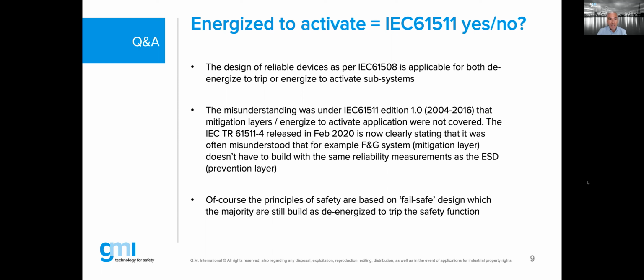Now, if you use that sensor in your area where the gas is available in a certain quantity, the purpose of the sensor is, of course, to sniff and recognize the gas. If the gas is blown by the wind in the wrong direction and there is no coverage by your gas sensors, that will not make the sensor reliable, because the sensor cannot even measure it. So the coverage, the mapping of your sensors, is just as important as the SIL2 on that specific device. But what is SIL2 on that device saying? That, provided the sensor is able to sniff it and recognize the concentration of gas in that area, that signal needs to be correctly provided to the control platform, and that makes it a reliable sensor. Not the mapping. The mapping is another issue, which has nothing to do with the SIL. That's another topic. But here it is about the reliability of such specific examples.